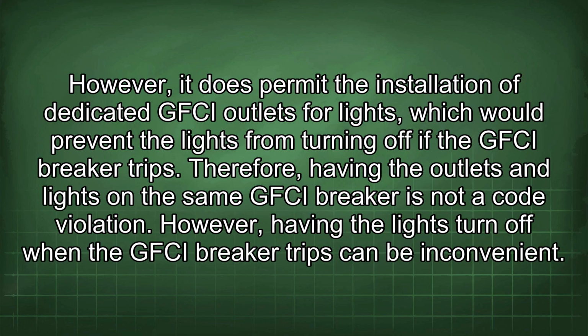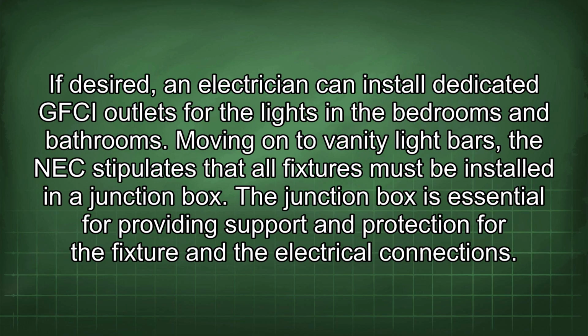However, it does permit the installation of dedicated GFCI outlets for lights, which would prevent the lights from turning off if the GFCI breaker trips. Therefore, having the outlets and lights on the same GFCI breaker is not a code violation. However, having the lights turn off when the GFCI breaker trips can be inconvenient. If desired, an electrician can install dedicated GFCI outlets for the lights in the bedrooms and bathrooms.